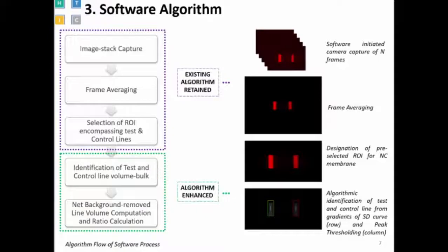On the software algorithm side, some algorithms have been explained in previous publications, so I will not go too deep into those. They mainly involve capturing and analyzing the image. In this particular paper, we explain our enhanced algorithm which removes the background flow — basically the background of the cartridge — which improves our output dynamic range of the instrument.